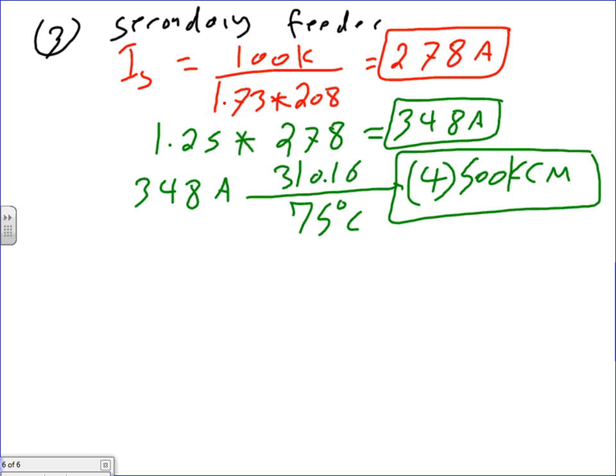And you guys are going to be later on when you start with the load. How do you size it even? How do we come up with 100K? Why not 200? Why not 300? How would you come up that I need a 100 kVA transformer? Start with the load. Always start with the load. You take your load, multiply the continuous by 1.25, keep adding them up, you come up with 100 kVA. Now that 100 kVA includes the continuous. Then, if you do it this way, guys, you don't have to multiply again by 1.25 because it's already incorporated in the transformer. That's how you do it.